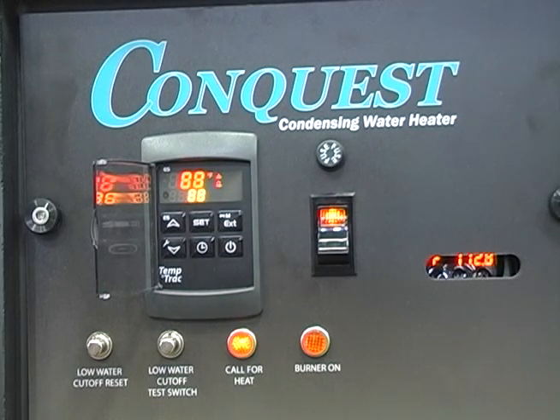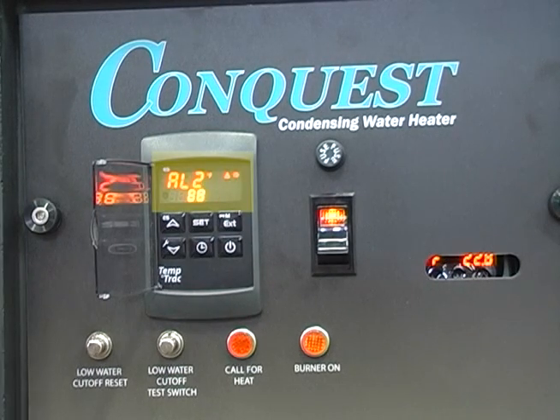The burner should fail to ignite due to no gas supply, and the burner will retry for ignition 2 more times before locking out. The 3 tries for ignition prior to lockout will take about 5 to 7 minutes. Lockout is confirmed by an AL2 alarm indication on the Temp Trac operating control. To reset the unit, cycle the main power switch.